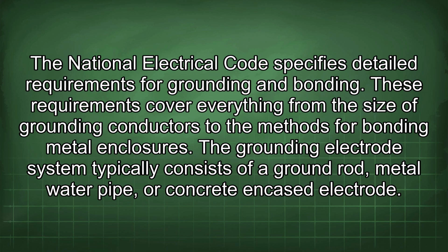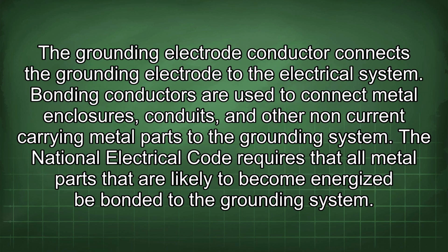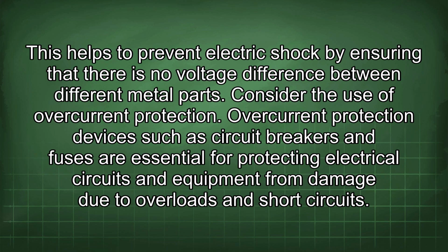The grounding electrode system typically consists of a ground rod, metal water pipe, or concrete encased electrode. The grounding electrode conductor connects the grounding electrode to the electrical system. Bonding conductors are used to connect metal enclosures, conduits, and other non-current carrying metal parts to the grounding system. The National Electrical Code requires that all metal parts that are likely to become energized be bonded to the grounding system. This helps to prevent electric shock by ensuring that there is no voltage difference between different metal parts.